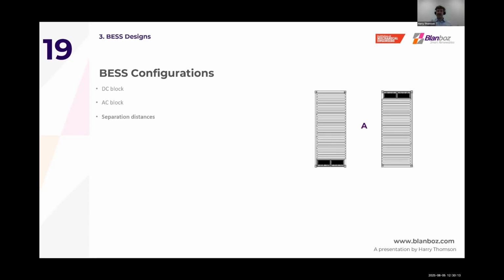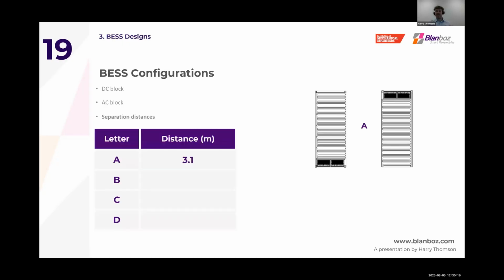We've got 2 battery containers here, with A being the distance between the open sides, where the doors open up, and we recommend this being a distance of 3.1 meters. This is also to do with fire separation, but to allow for access into the battery modules.